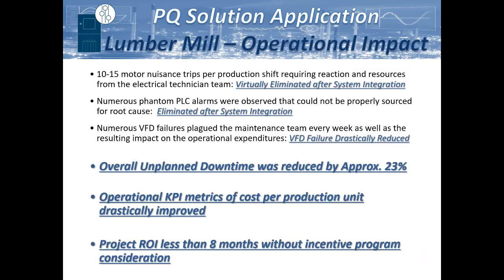But what was more impactful to the operation was actually the impact that it had on production. So at this facility, they pretty much had an electrician per shift whose main purpose was just to go around resetting breakers or resetting VFDs, because they were constantly having things trip out. And they'd have phantom alarms that they couldn't quite figure out. They'd have to stop the process, reset it, get it going again. And they'd have at least one VFD failure per week, and they just really hoped it wasn't an important one.